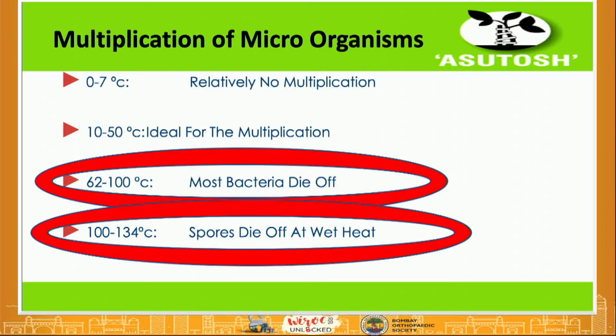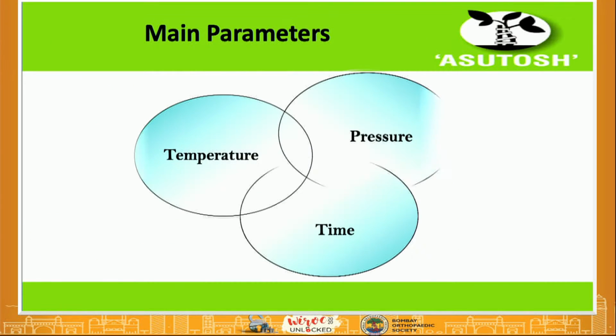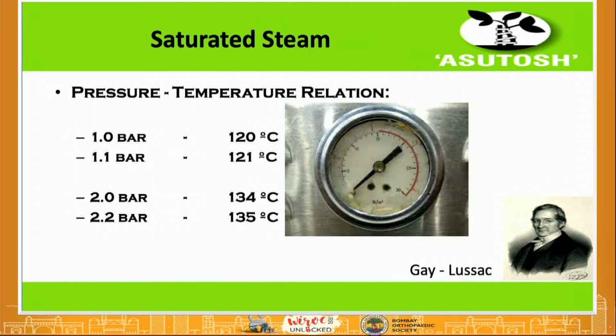The multiplication of the microorganism, when it concerns the spores, the death of the spore occurs after 130 degrees. So high heat is mandatory to kill the spores in addition to the vegetative organism. Now, three parameters are interlinked with each other: the temperature, pressure, and the time.